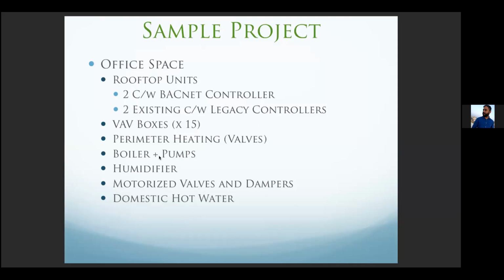Boilers and pumps, same way. Typically boilers would be proprietary or Modbus even in some cases, and they talk Modbus amongst themselves, for example, and then it may have like a BACnet card that you are able to pick up. If that is not the case, you may need to look into providing a controller, hardwiring all the points as required to program whatever you need to program, and integrate it that way.